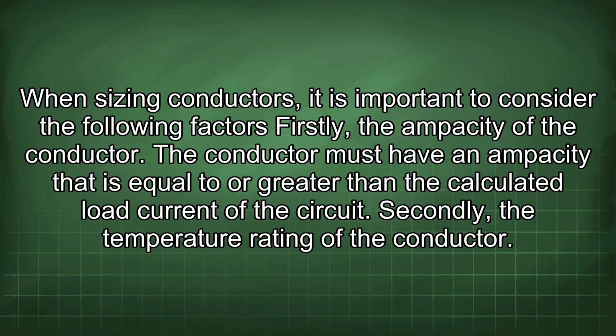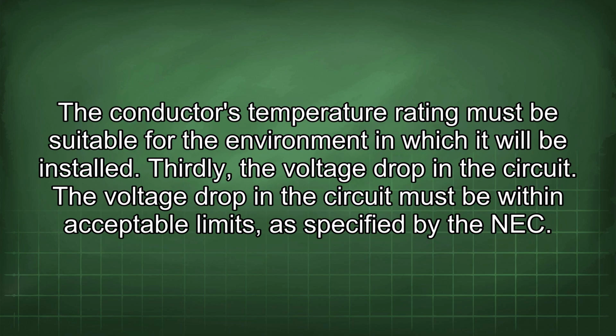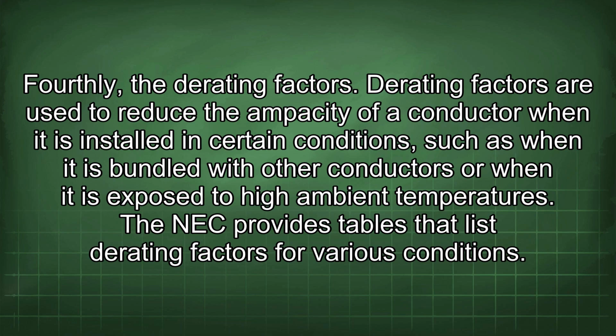Firstly, the ampacity of the conductor. The conductor must have an ampacity that is equal to or greater than the calculated load current of the circuit. Secondly, the temperature rating of the conductor. The conductor's temperature rating must be suitable for the environment in which it will be installed. Thirdly, the voltage drop in the circuit. The voltage drop in the circuit must be within acceptable limits, as specified by the NEC. Fourthly, the derating factors. Derating factors are used to reduce the ampacity of a conductor when it is installed in certain conditions, such as when it is bundled with other conductors or when it is exposed to high ambient temperatures. The NEC provides tables that list derating factors for various conditions.